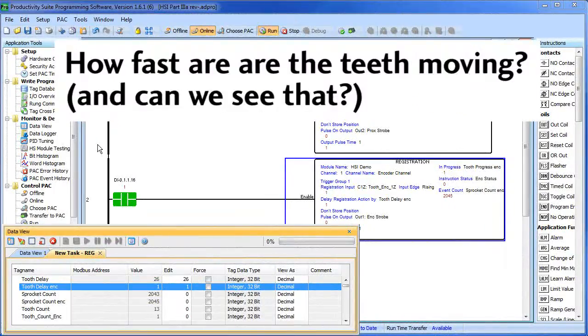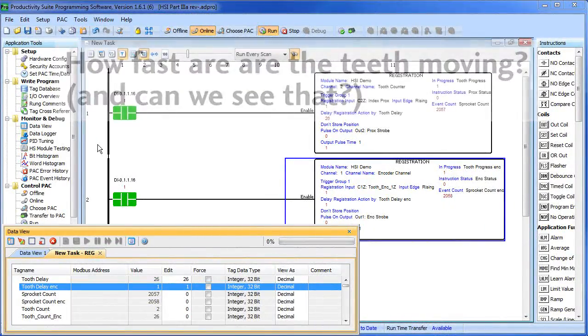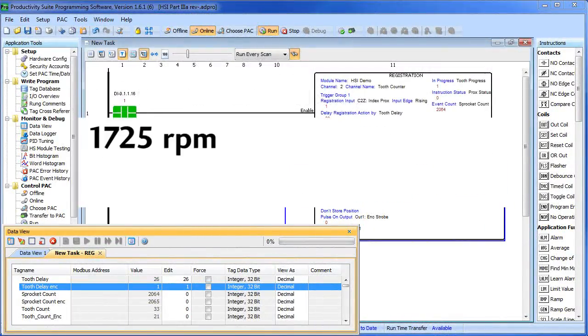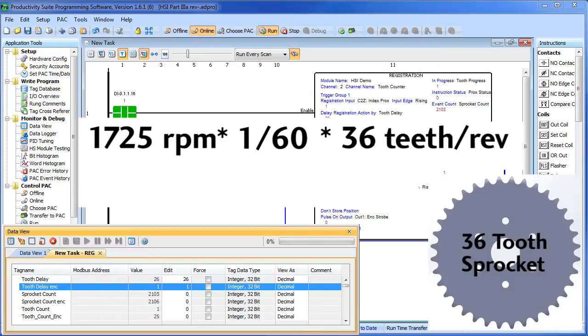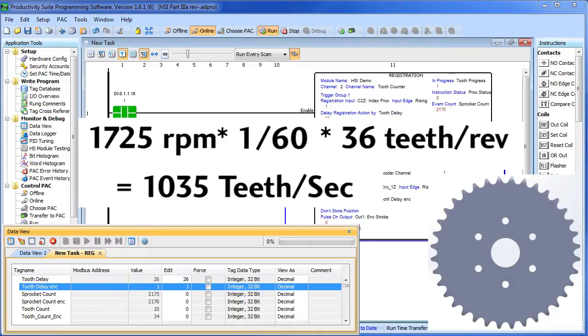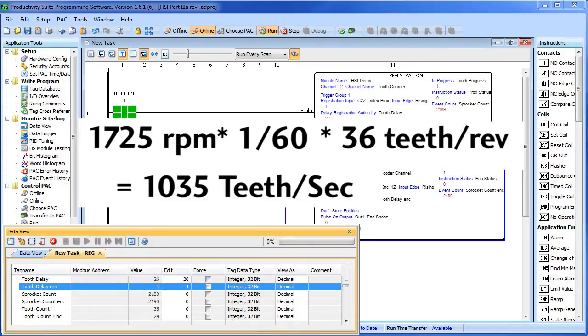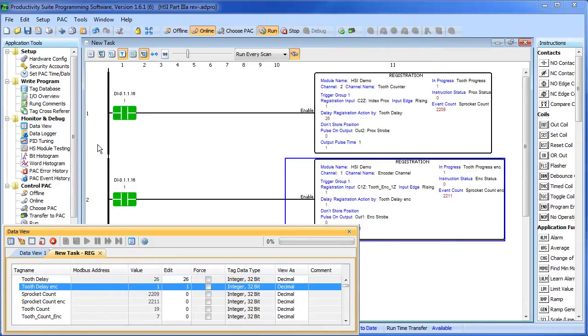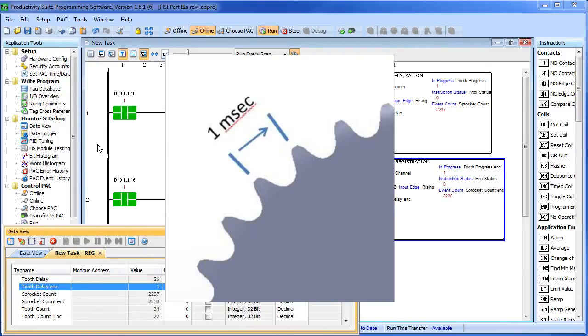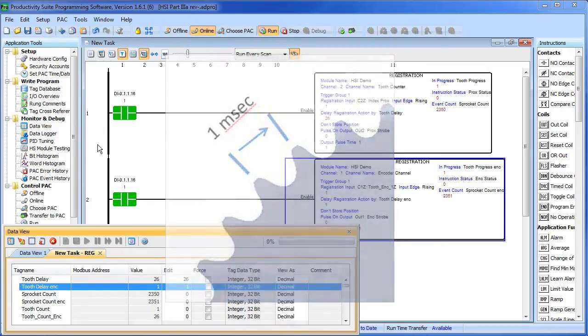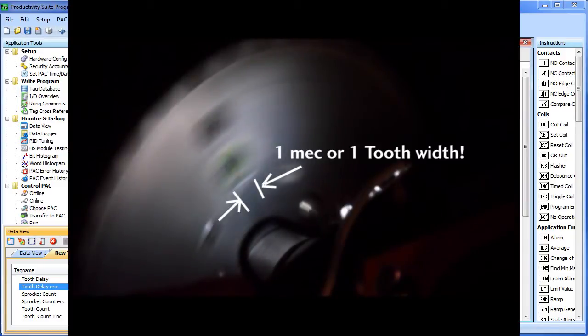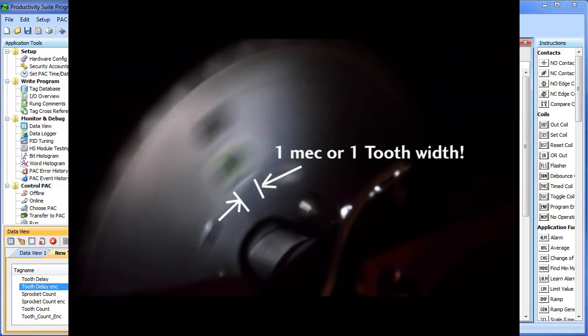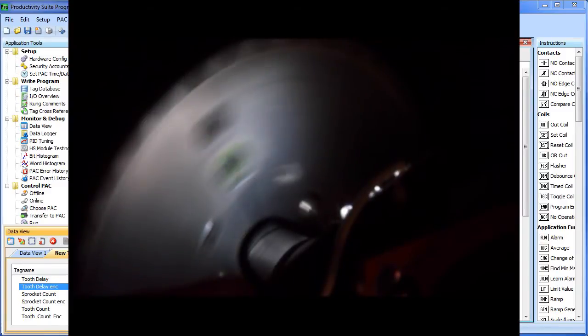How fast are these teeth moving? Well, we have a motor that can run at 1725 RPM and if we convert that to revs per second and multiply that by the 36 teeth that we have per revolution, we'll get roughly 1000 teeth per second going by. That's about one tooth every millisecond. And remember, our strobe width was also one millisecond. So while that strobe light is on, a tooth will travel a little over one position during the strobe pulse duration when the motor is at full speed. Can we see that? Sure. Let's crank up the motor speed to 1725, bring up the strobe light and sure enough we can see the blur of the tooth sweeping through the 1 millisecond of time or about one tooth width. That's pretty cool.